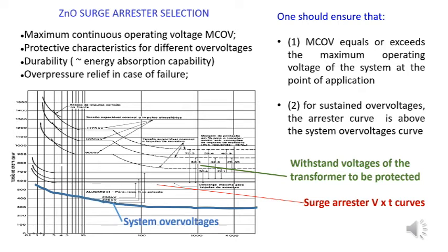Taking a look at this figure, in the left bottom side, we show in a stylized way the curves representing the overvoltages which occur in the system — the long duration and short duration ones. Let's suppose that we did an insulation coordination study and detected the levels of lightning impulse, surge impulse, and temporary overvoltage. For each value of overvoltage, we checked the corresponding duration and constructed a curve similar to the blue one shown.